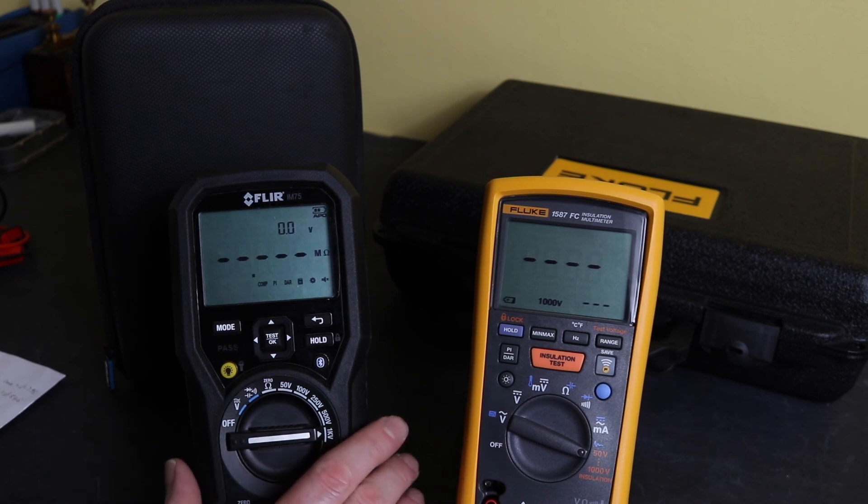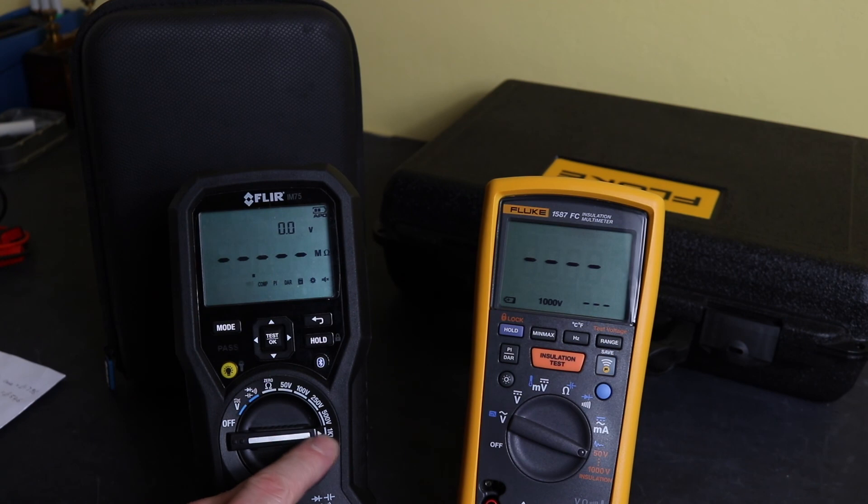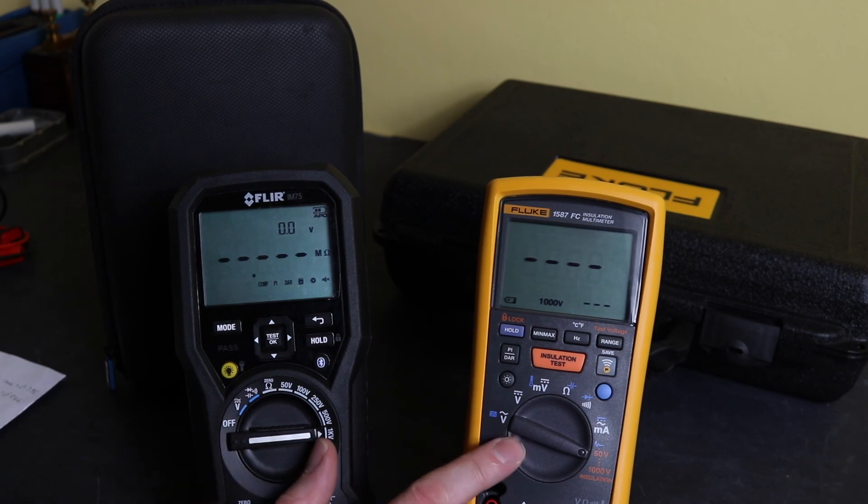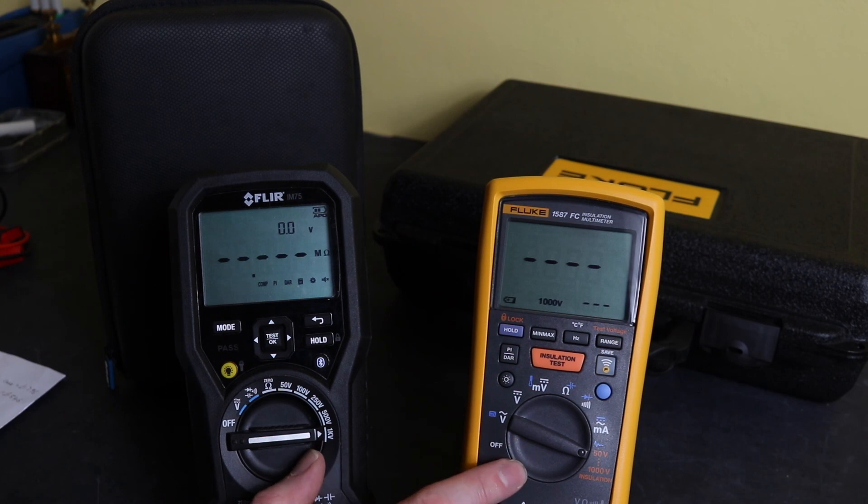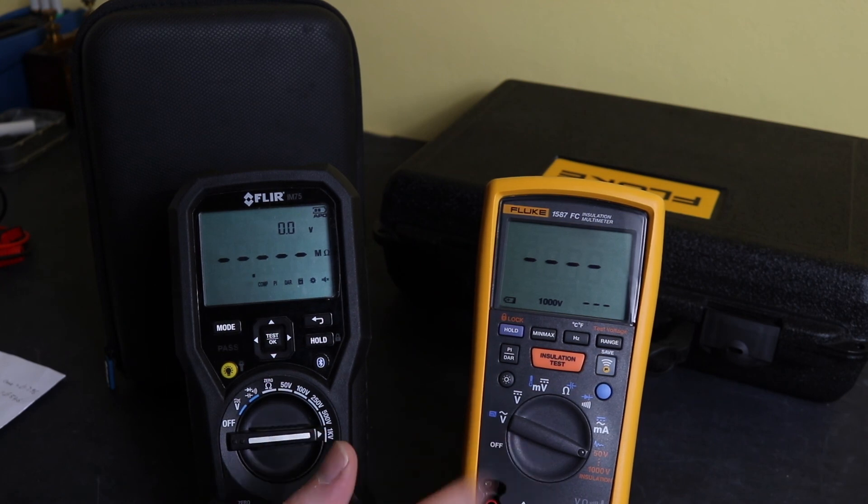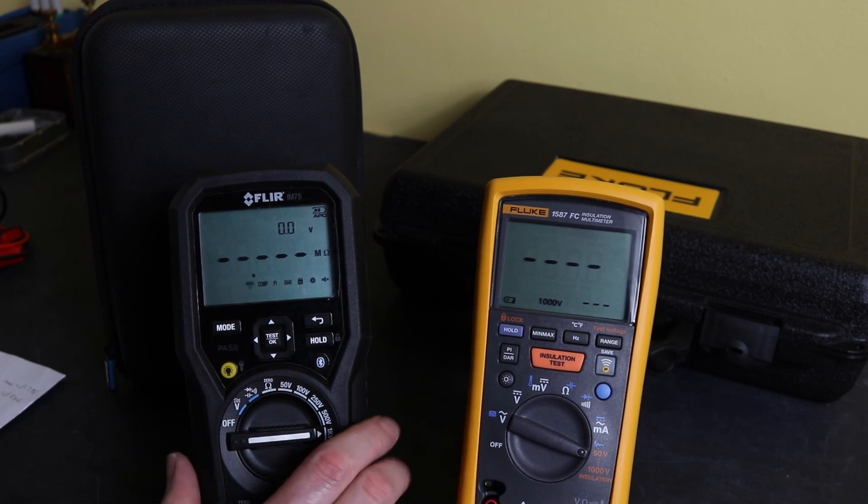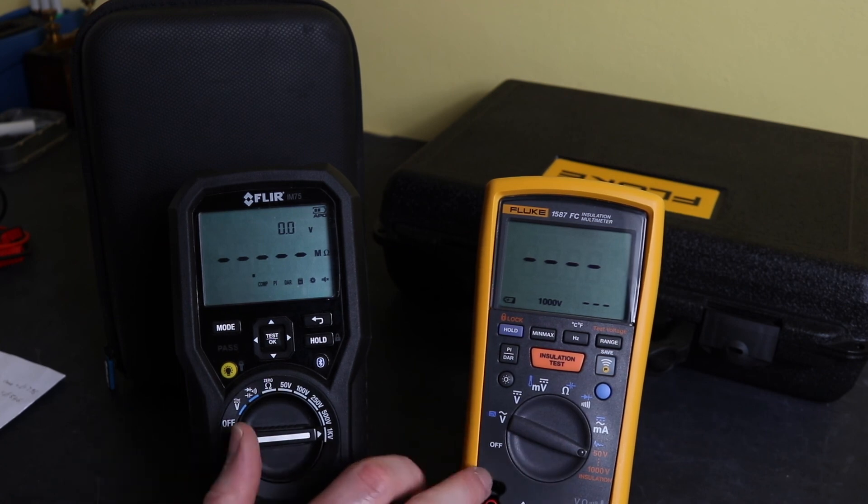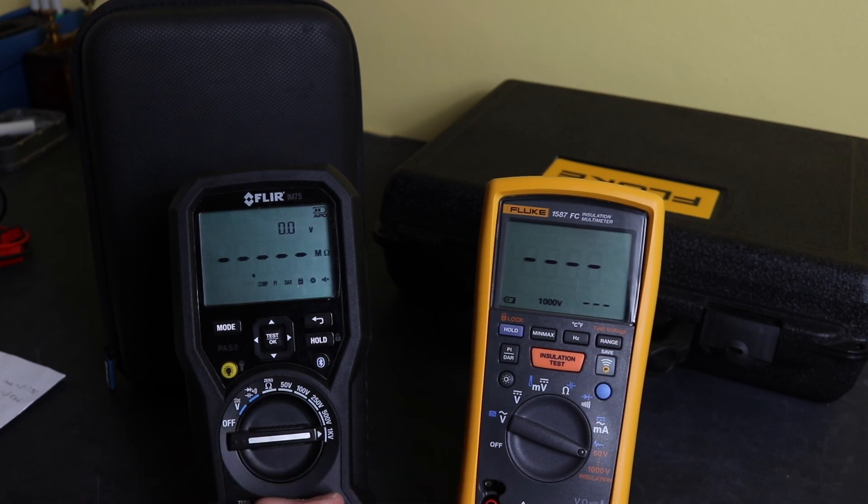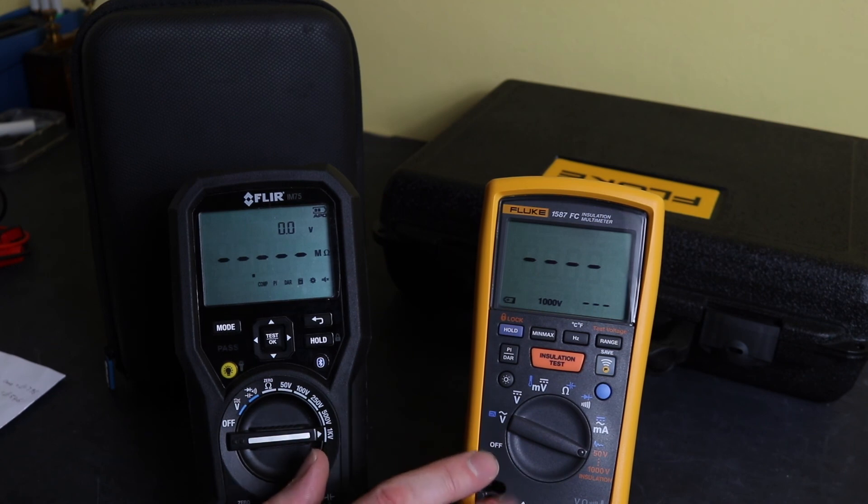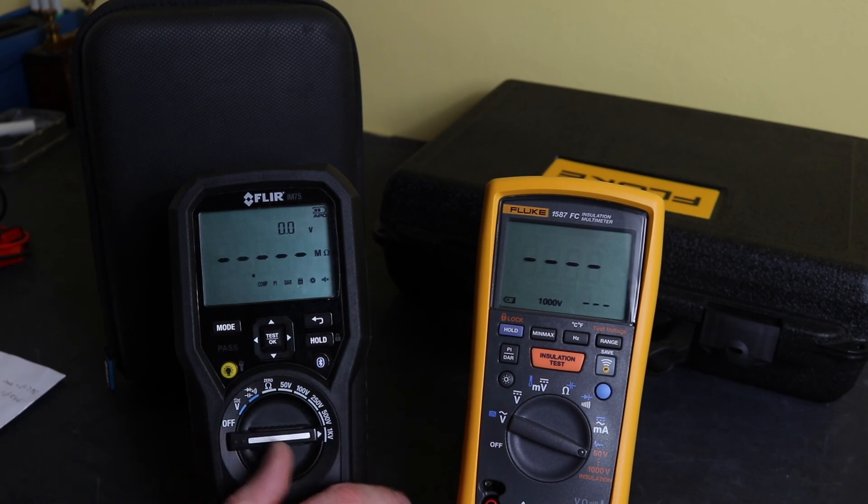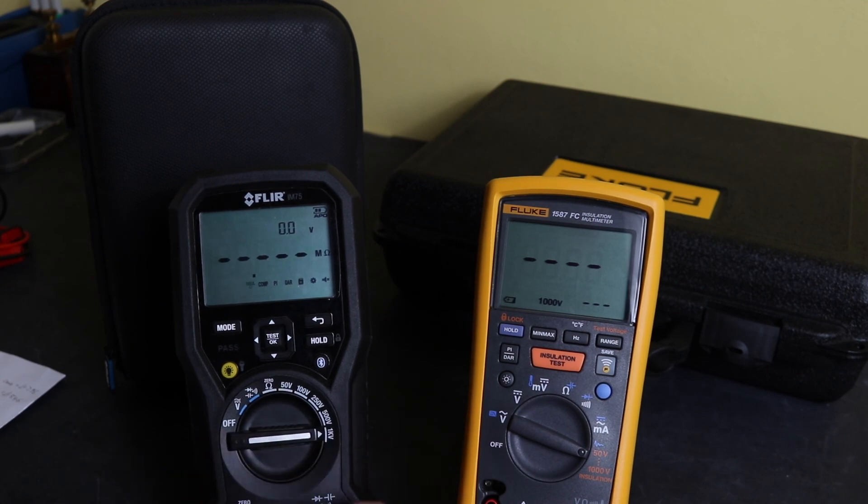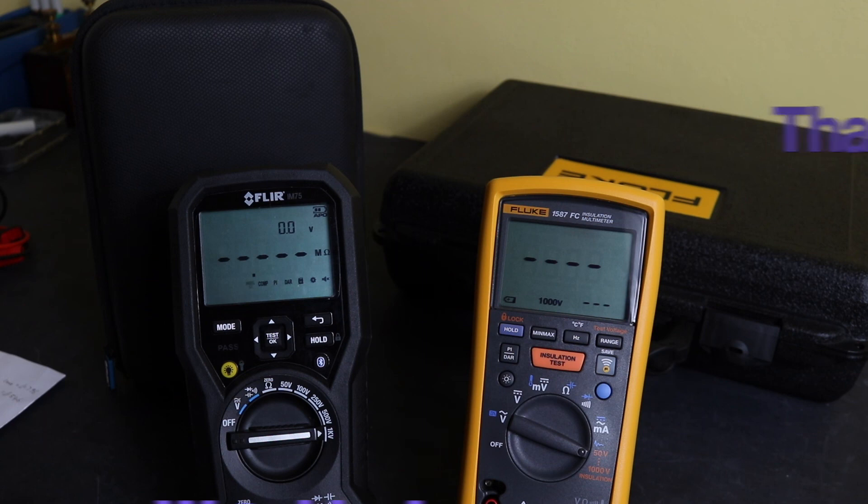So although the Flir offers an extended testing range for the insulation function, that is only at 1000 volts. When you drop it down to 500 volts, both instruments are comparable, and the vast majority of my testing will be done at 500 volts or below. It's usually only cables I'll test at 1000 volts. So the extended range the Flir offers against Fluke has limited advantages in comparison really. Yeah, so for me I would probably go down the route of the 1587 FC in preference to the Flir IM75. And so that's pretty much it for this video. Thanks for watching, hope you found it useful, and I'll see you again in another video.